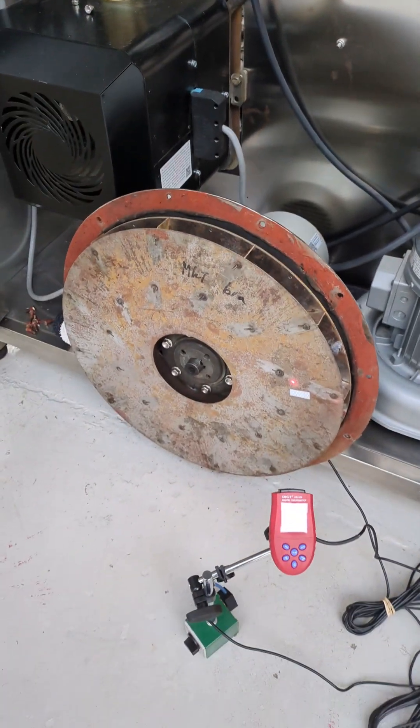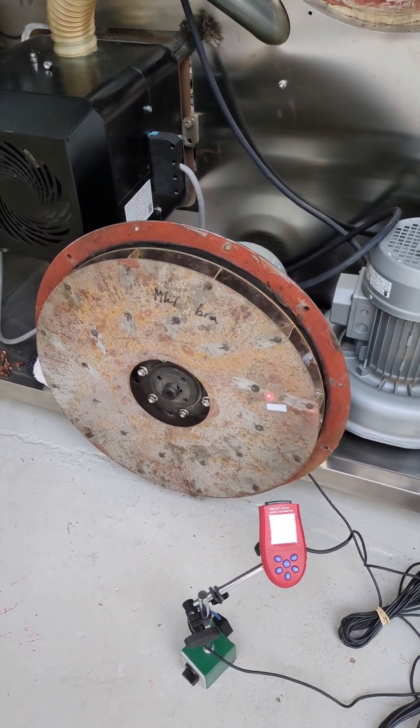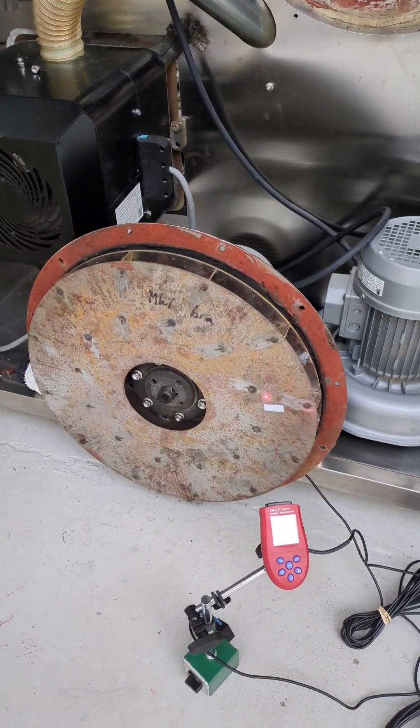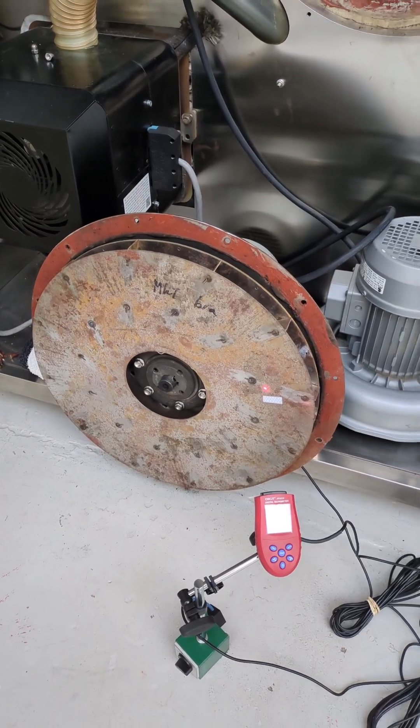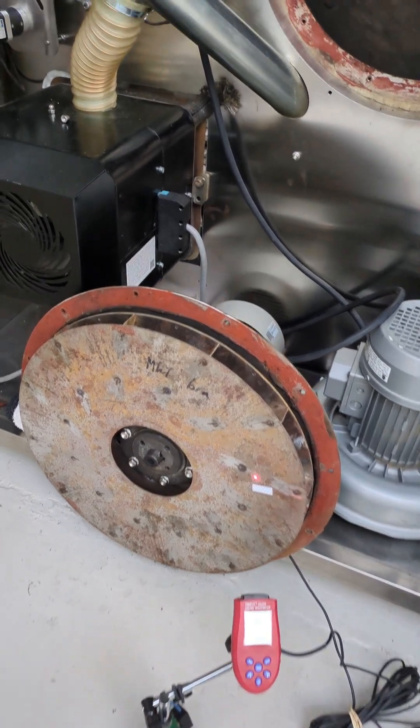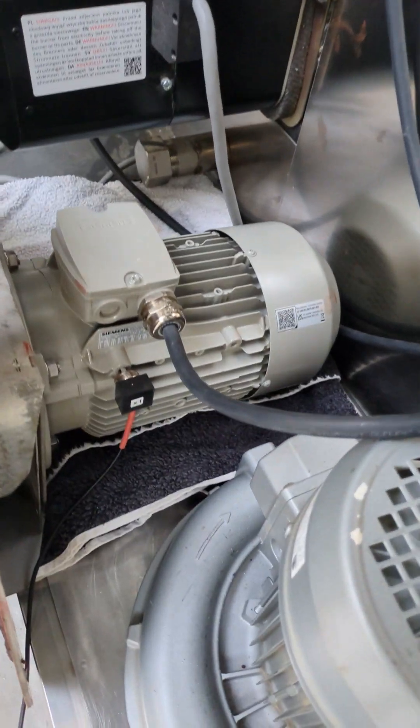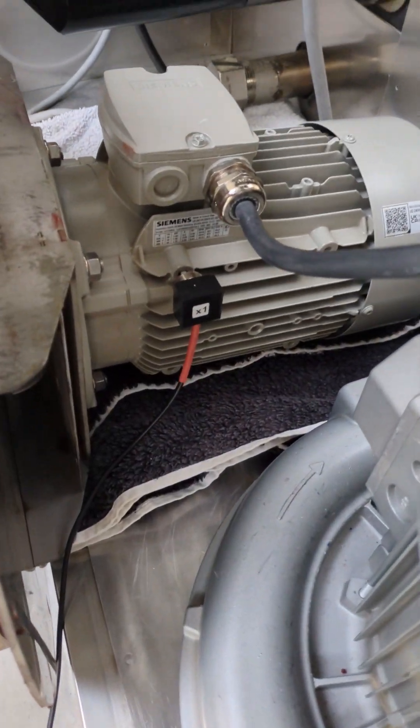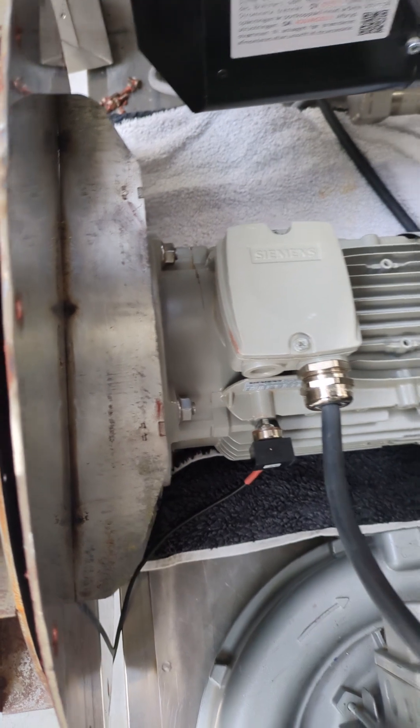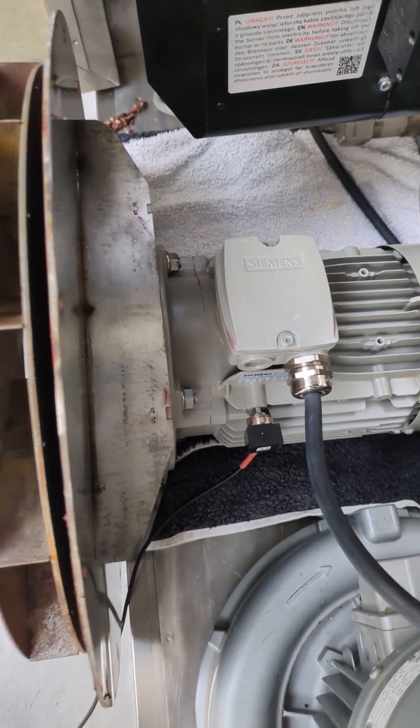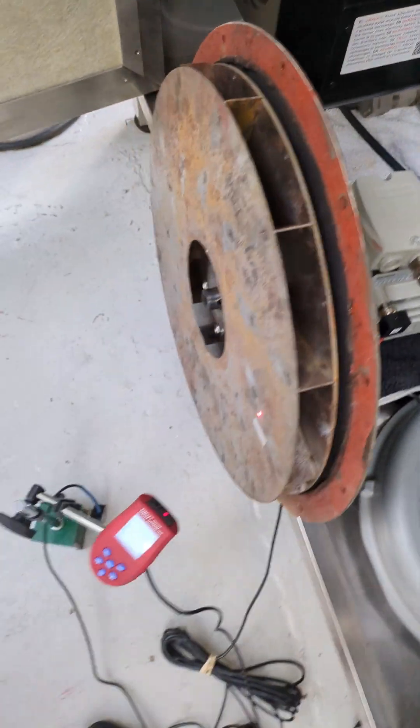Vibromera Balanset-1A in the field. A seven kilo centrifugal fan wheel 450 millimeter diameter 30 millimeter wide. Sensor 1 connected properly on the engine or the electric motor rather.